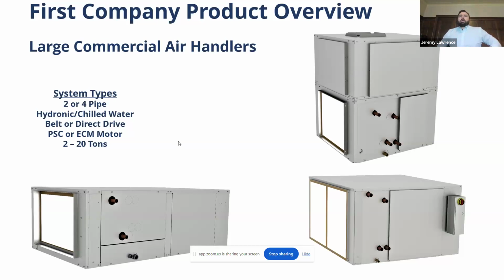So where First Company has found a niche inside the GTA is these units. These are most commonly installed in all the amenity areas, right? When you need a bit bigger of a system, and they can be designed to the space. So either 2 or 4 pipe, hydronic chilled water, belt or direct drive, ECM or PSC, and a huge range of 2 to 20 tons, depending on all the applications in the building.